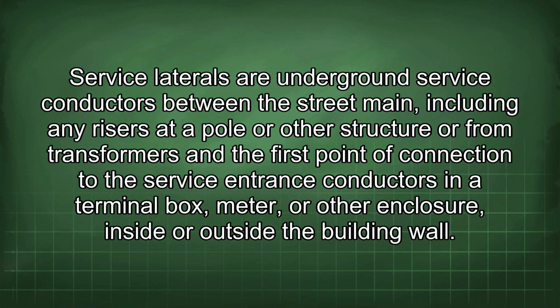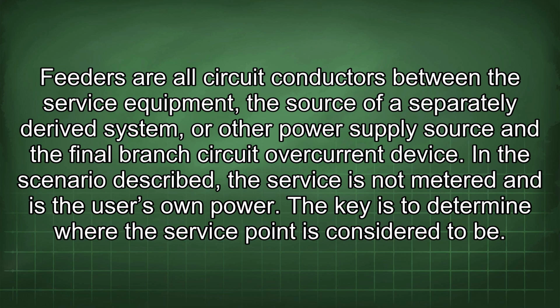Service laterals are underground service conductors between the street main, including any risers at a pole or other structure, or from transformers, and the first point of connection to the service entrance conductors in a terminal box, meter, or other enclosure inside or outside the building wall. Feeders are all circuit conductors between the service equipment, the source of a separately derived system or other power supply source, and the final branch circuit overcurrent device.